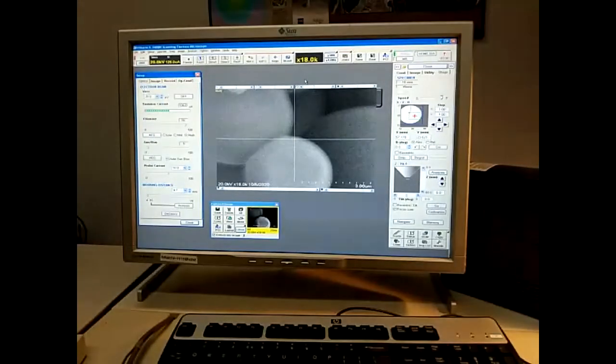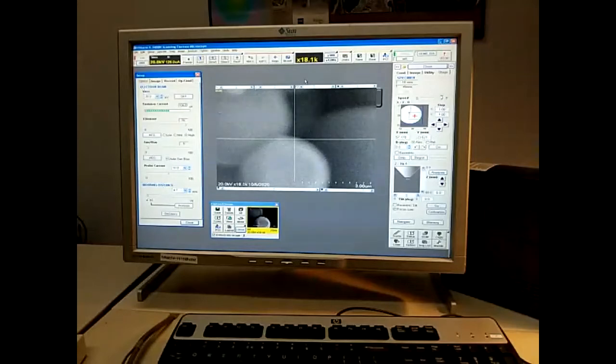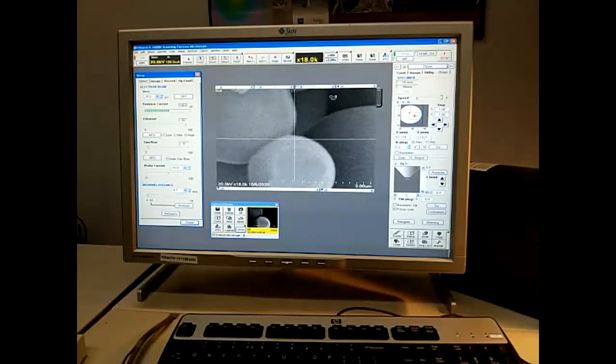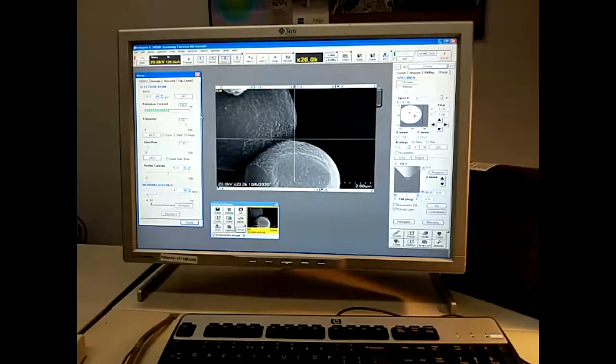Starting the video again, you can see that taking it down to an aperture three and a probe current of 50, it's quite bright. Here's your auto brightness and auto contrast setting. Doing a little bit of focus. And you can see by the movement that when we change these settings, I'm going to have to do a little bit of alignment on the machine, which is quite normal.